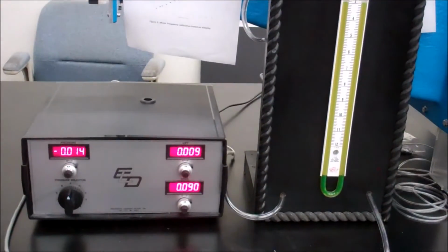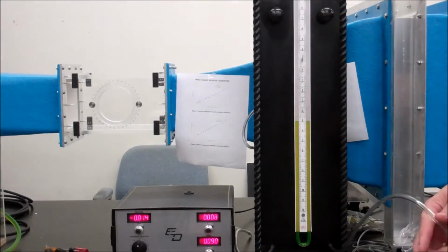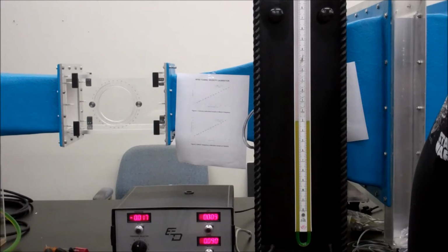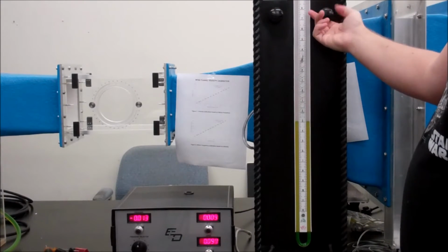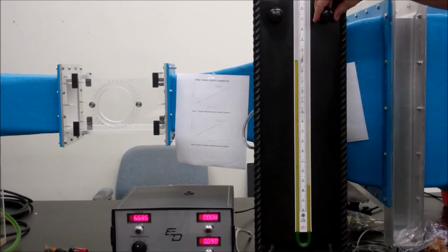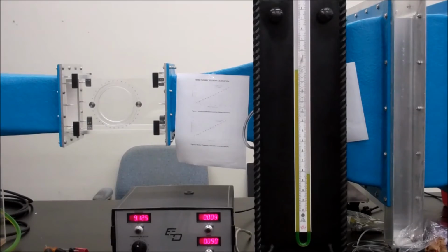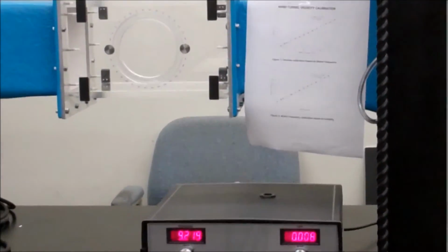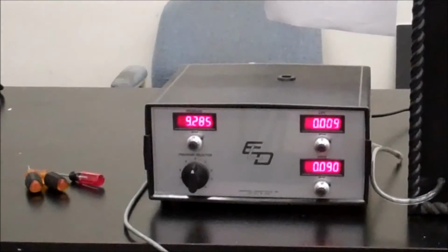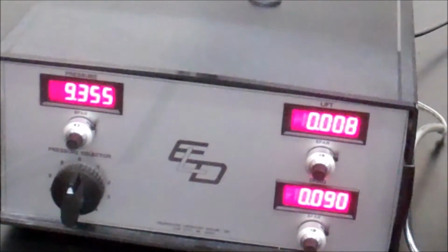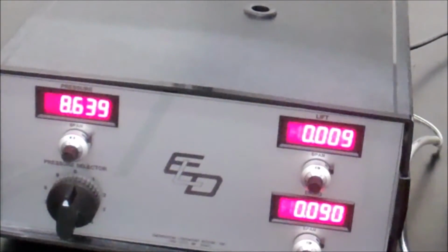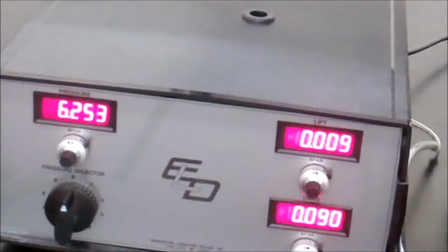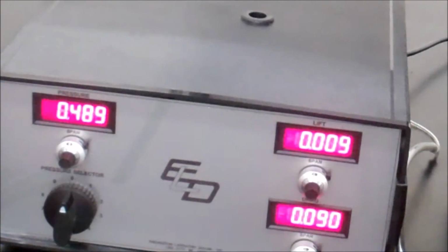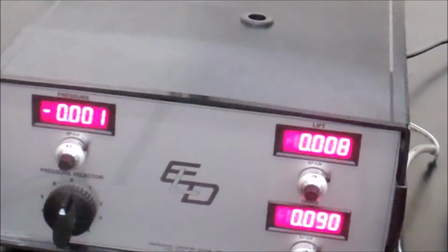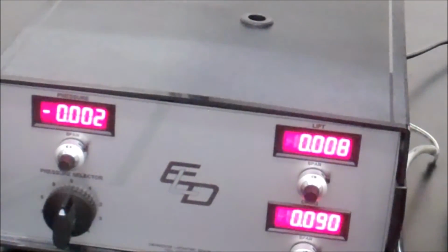And you're going to calibrate it in the same method we calibrate the pressure transducers for Bernoulli's lab. So you're going to pump up to 10 inches of water column. That's the maximum you need for standard pressure transducer calibration. So you're going to go ahead and close your vent, open your pump, then pump it up to your 10 inches of water column. Then you're going to read the voltage on the display. You notice that it's changed to 9, and then you go down some more and you read your voltage and keep on doing that, and you'll get your voltage respectively. And it should go back to your 0.